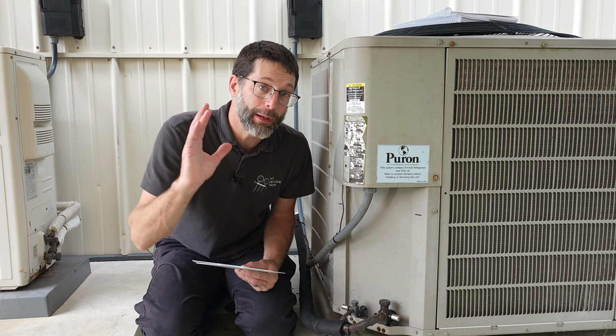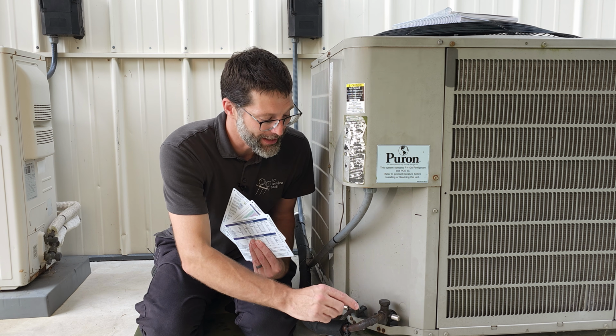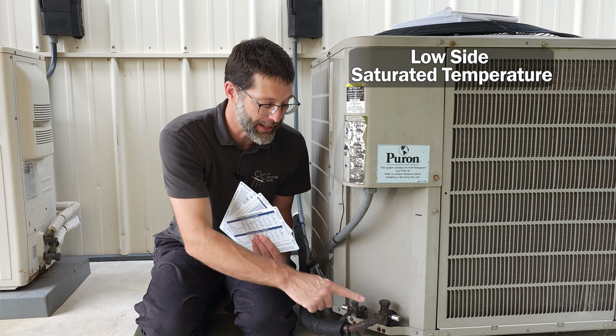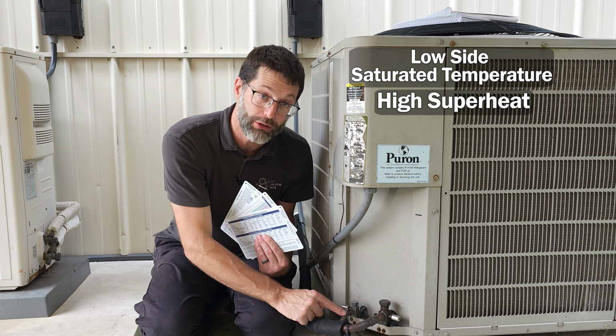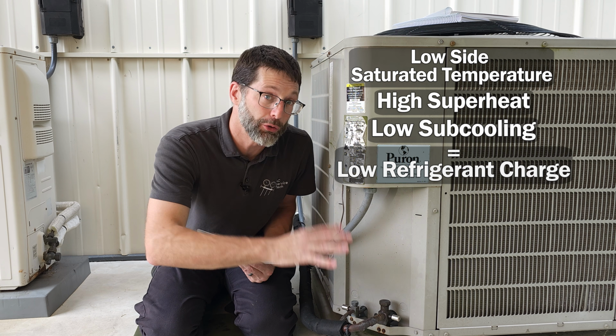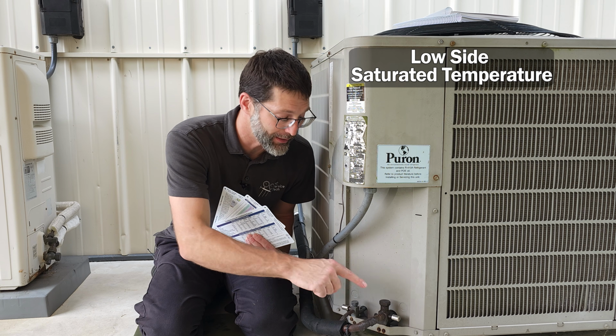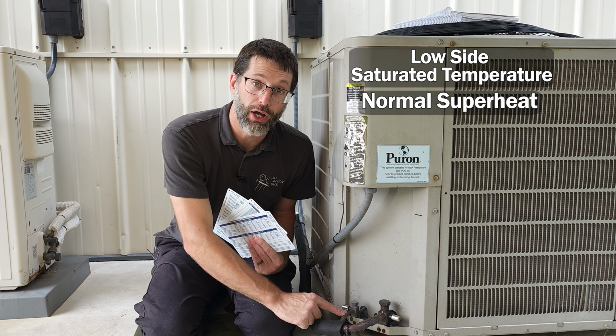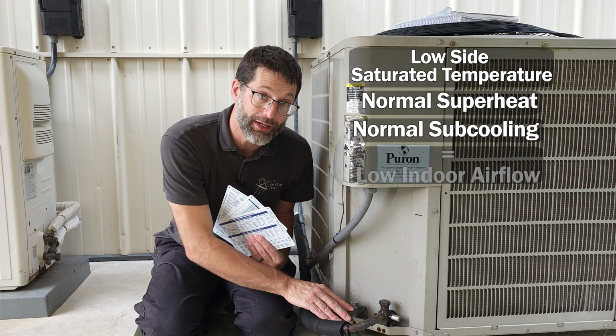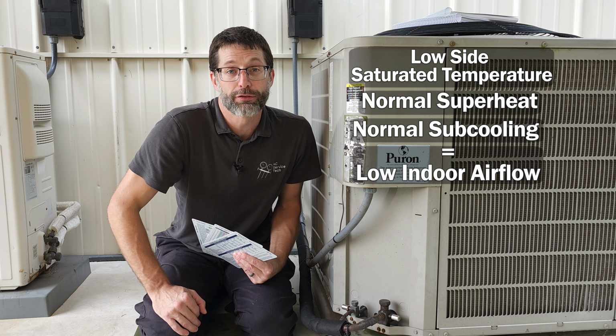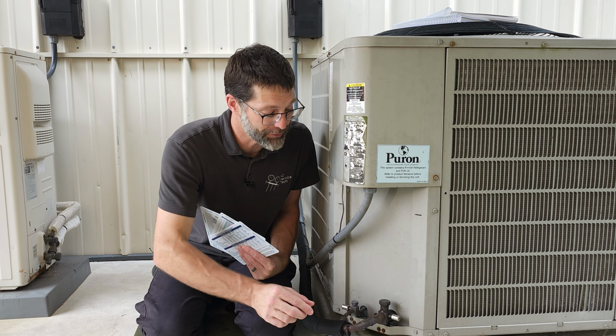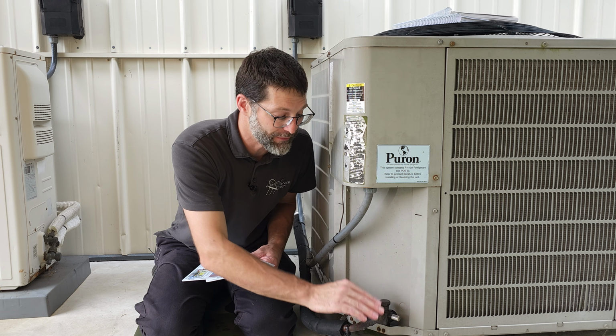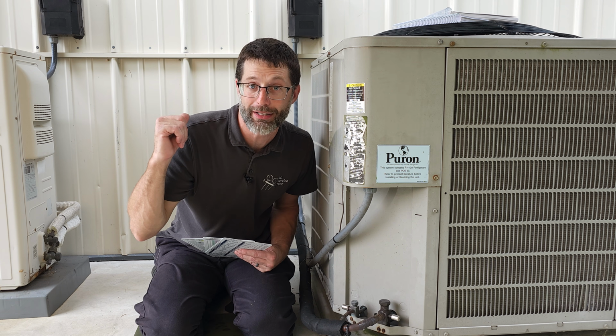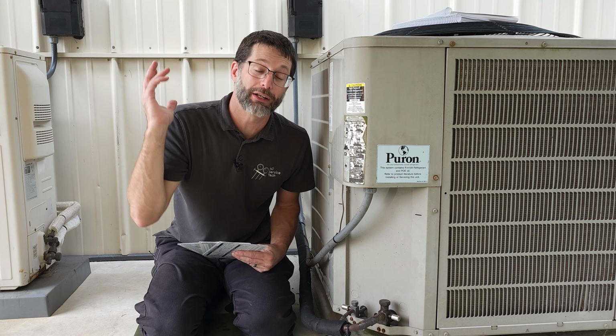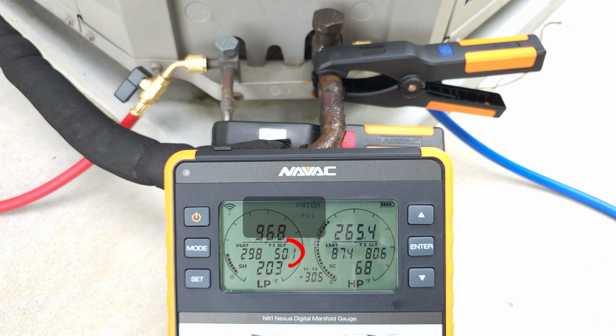So that's it. So just remember, as far as indicators go, you can have a low side saturated temperature and also a high superheat and a low subcooling. That would indicate that you have a low refrigerant charge, but low airflow is a low sat temp, average total superheat, and then also on the liquid line, you're going to have a normal subcooling. And so a liquid line restriction differs from low airflow because it'll have an extremely high superheat where the vapor line temperature will be about the same as what's inside the building. So that will be as high as, say, 70 degrees. In this case, we had a vapor saturated temperature right around 50 degrees or something like that.